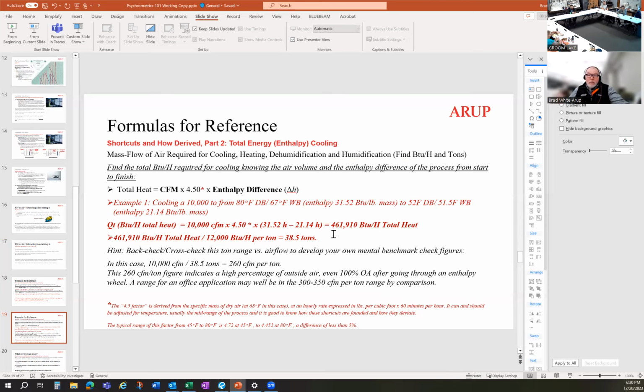With mixed air you have multiple processes. You'll have energy recovery thrown into the mix, taking a lot of energy out, and you wind up with 2 or 3 airstreams mixing together. You have to figure out how well mixed that airstream is, bring it through a cooling coil, through filters, through the whole process and out into the space. This breaks it down into a smaller chunk so you can see where these numbers come from.